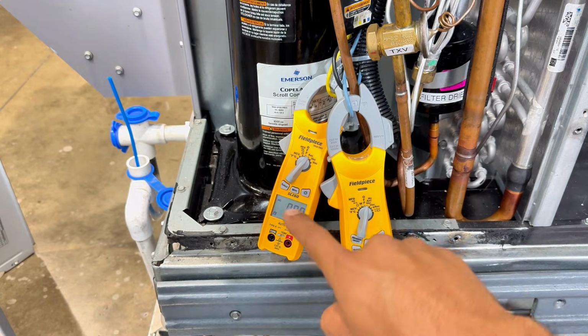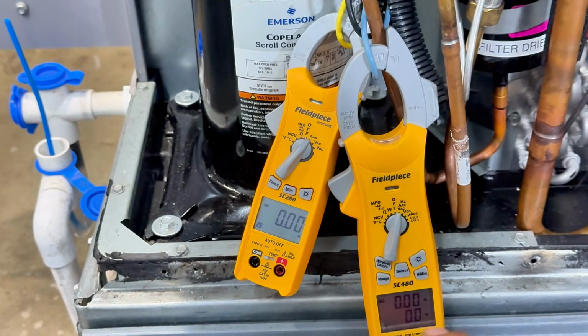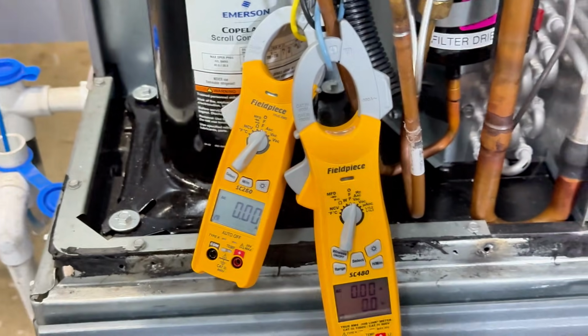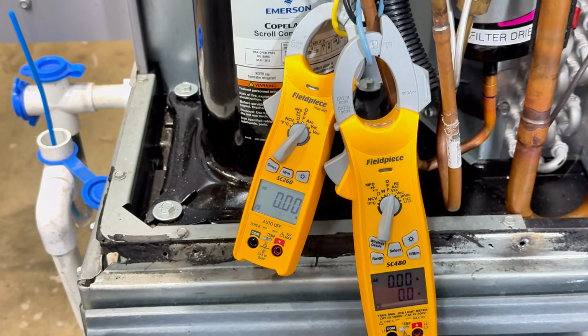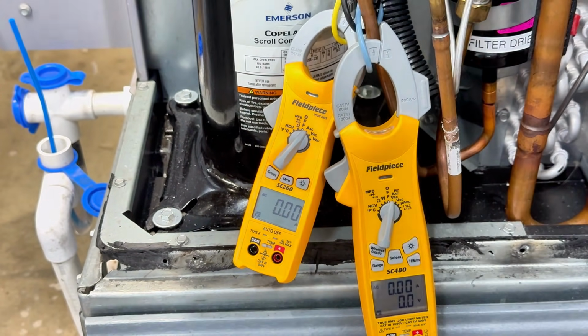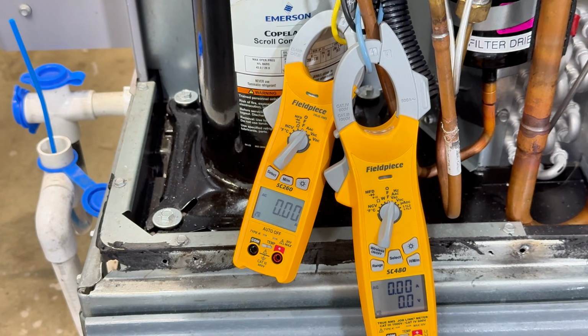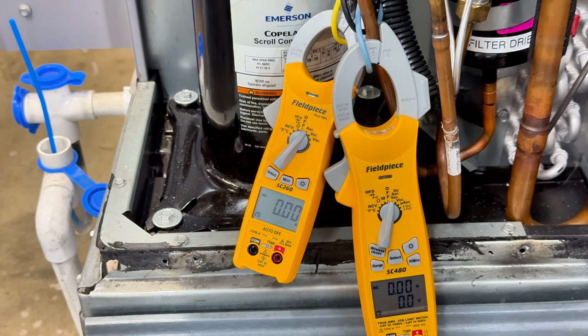So keep an eye on this one right here. Okay, I'm going to go ahead and call for cooling. I want you to keep an eye on that and see the inrush current. And it's going to be in a split second. So you've got to check it out pretty fast.